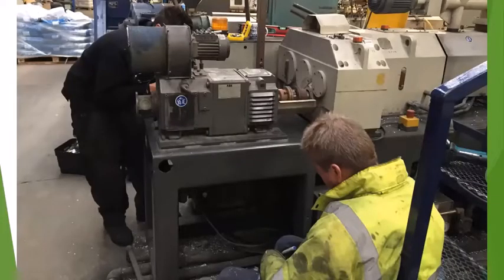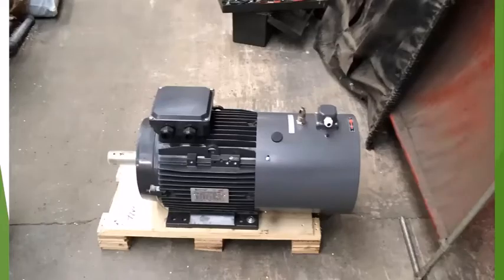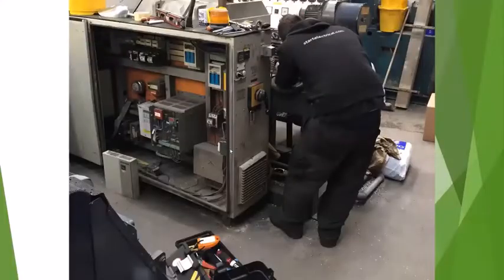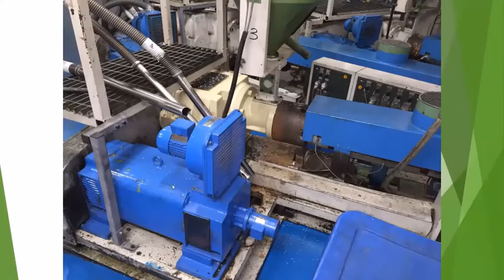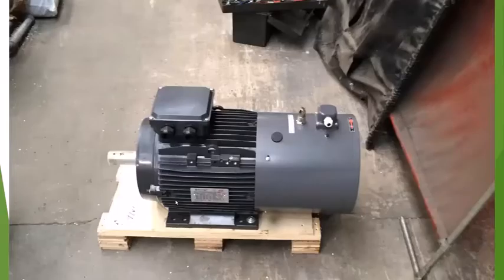What you might want to talk about is also the airflow that goes over the motor. You can see on the other machine, this is a DC machine, but they have this blower that pushes the air right through the motor and then expels it out over here. So that doesn't require the cooling to be blown over here. Here, there's no airflow inside the motor other than just a small amount internally. And so that's why the frames tend to be heavier and bigger.